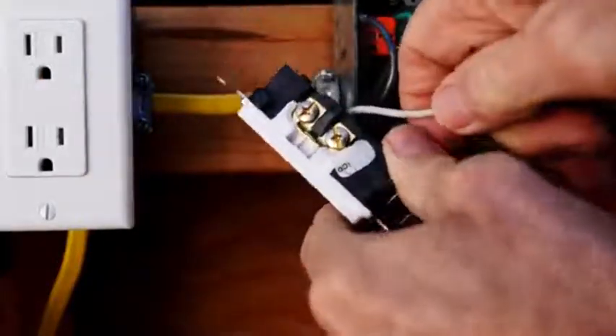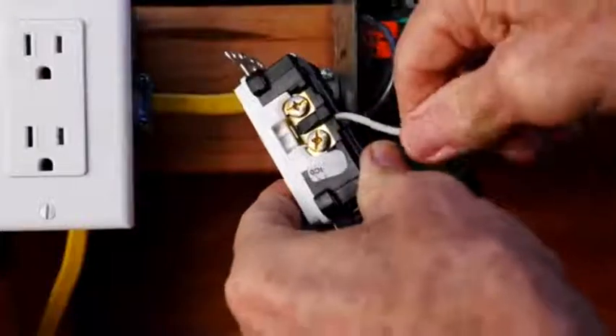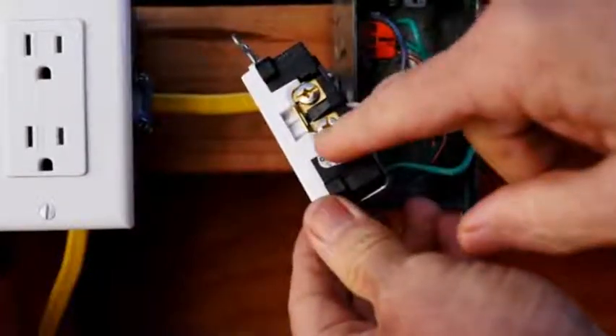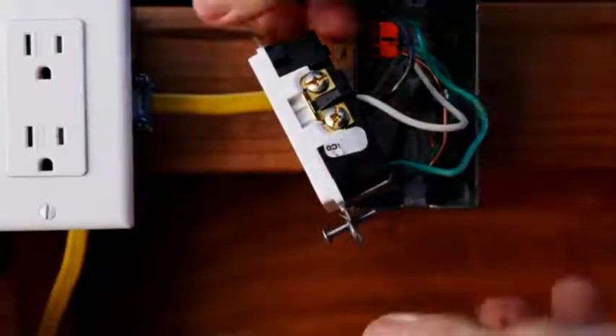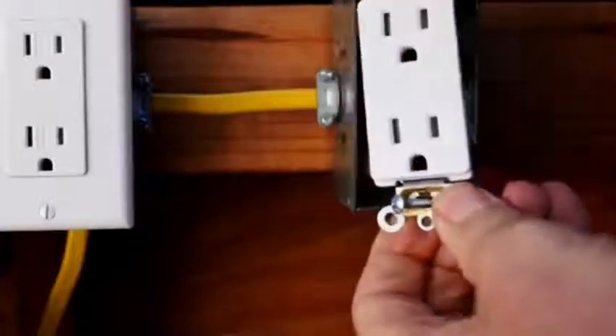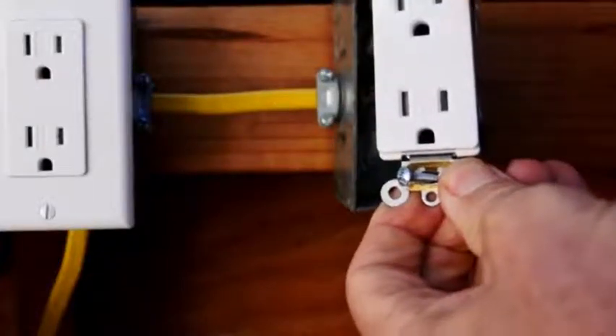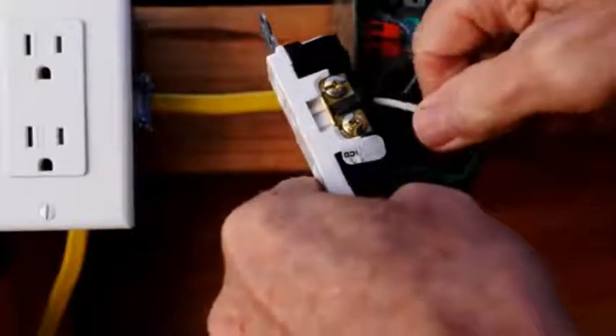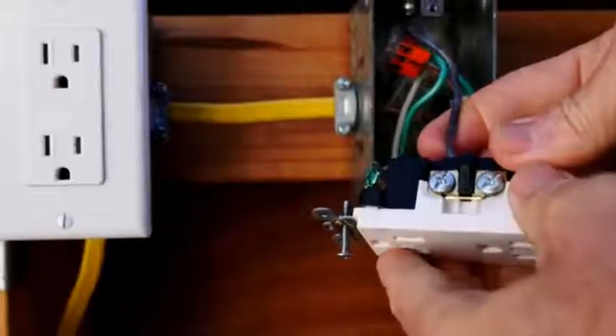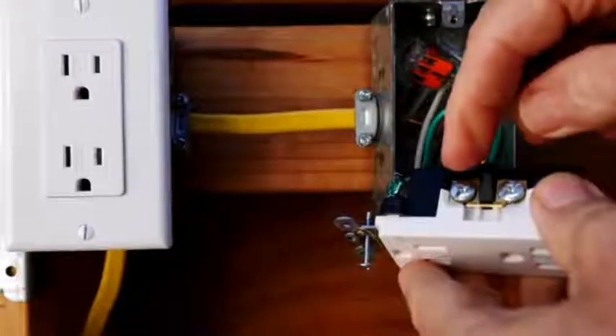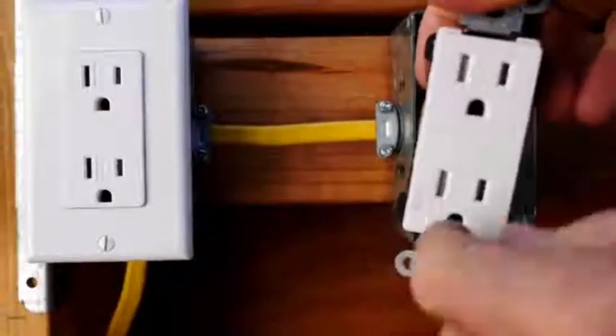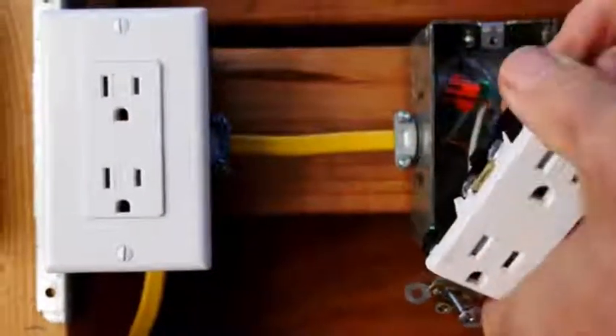Okay, we have the white neutral wire going to the bronze colored terminal. That's incorrect. You see, the hot black wire must go to the short hot terminal side with the bronze colored terminals. And on this side, we have the white neutral wire going to the silver terminals, which is the side with the long neutral slot.